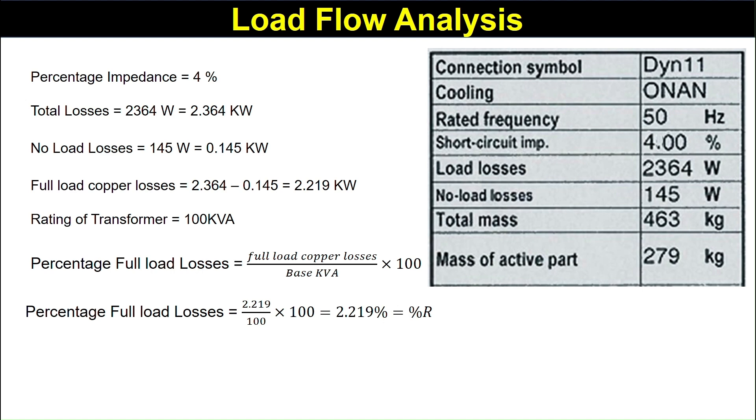Because it is a resistive load, the power factor is 1. So, the percentage R is 2.219 percent.